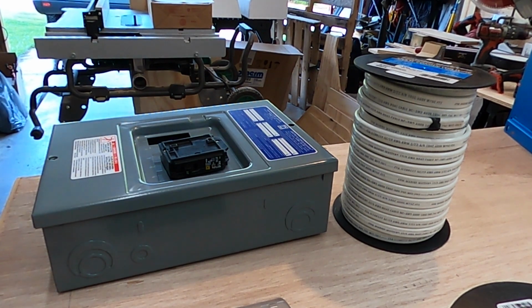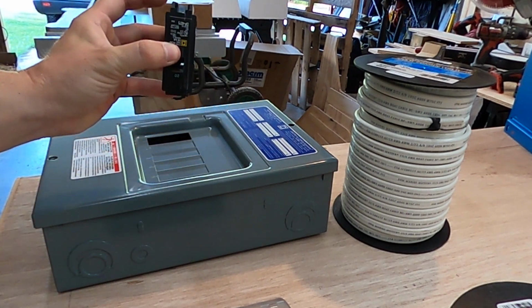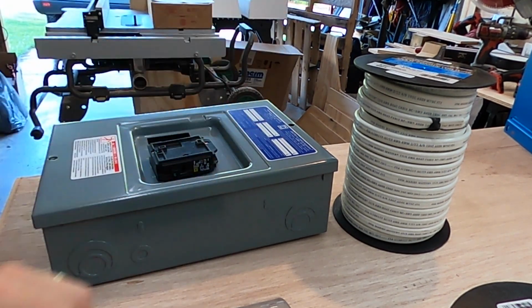So I spent the extra money and got the marine grade multi-conductor wire to run all of our AC loads. I went with 12 gauge solely because the AC unit is going to be on a 20 amp breaker and pull close to 15 amps, so the 12 gauge wire will handle that load. I could have probably gotten away with 14 gauge wire and 15 amp breakers on all my other circuits, but since I had to buy a 100-foot roll, I went ahead and got 20 amp circuit breakers to run 12 gauge wire everywhere.